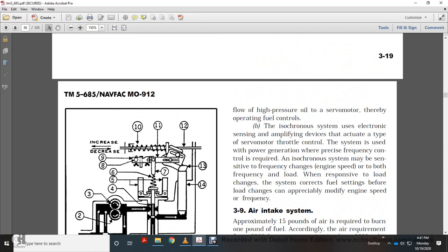The isochronous system uses electronic sensing and an amplifying device with a servo motor for throttle control. The system provides precise frequency control. Isochronous systems may be sensitive to frequency changes, speed changes, or both, and are responsible for correcting fuel settings before load changes can appreciably modify engine speed or frequency.